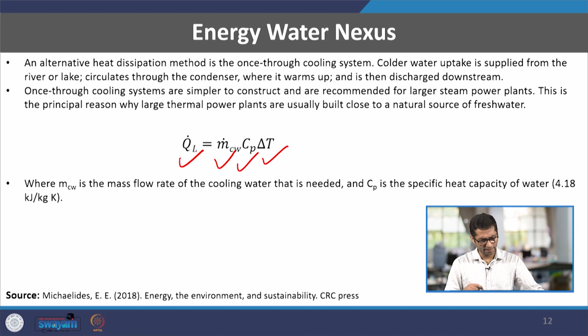Let us take a similar example. If I consider the same case of heat rejected being around 2000 megawatt, and use the same equation with the Cp of water being 4.18 kilojoules per kg Kelvin, assuming a delta T or temperature difference of 10 degrees Celsius -- meaning the difference in temperature from the source, from where the water is taken upstream to where it goes downstream -- the cooling water mass flow rate would be roughly 48,000 kgs per second. Remember, in the earlier case this was around 833 kgs per second, so there is a huge increase in the amount of water that needs to be circulated.